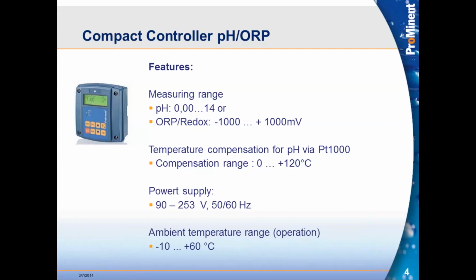The power supply for the compact controller is the universal power supply. They write that down as 90 to 253 volts, 50 or 60 hertz. They come up with that 90 to 253. That seems like a pretty specific number. That is 100 to 230 volts AC plus or minus 10% on either end. So that's how you get 90 to 253. And then, again, it's 50 or 60 hertz. We'll talk a little bit more about that on the next slide. The ambient temperature range, where it should be installed, is minus 10 to positive 60 C. We'll translate that for everyone. That's not a problem.